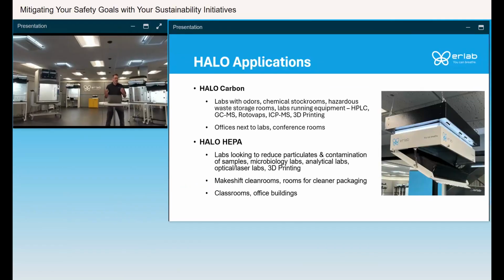And where would you install them? Well, in the lab world, the carbon filter version is kind of easy to know. You should install one because you can smell odors. You walk into a lab, it smells. There's probably something going on, whether the HVAC's at capacity, or you may have equipment in there that's not vented to the outside, where it's releasing chemical vapors and odors into the lab space. You may have hazardous waste storage rooms, or a chemical stock room where there's always odors coming off those bottles. So the Halo is a good option to install in those places to help increase the ventilation effectiveness of your current HVAC, and capture and remove those chemical vapors and odors.